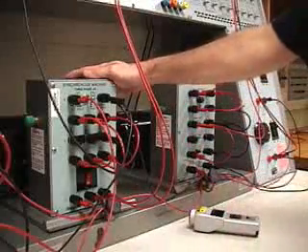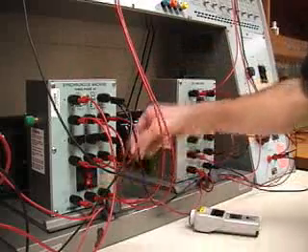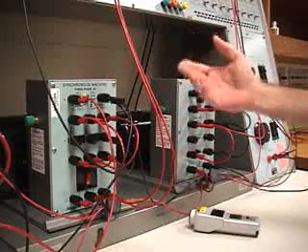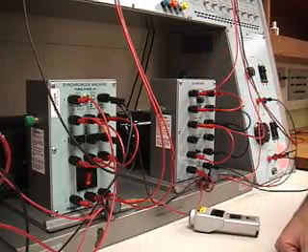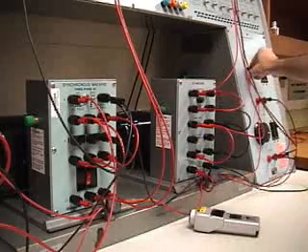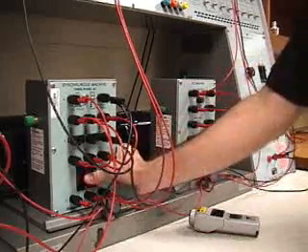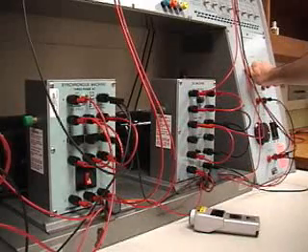In the startup of the three-phase synchronous generator, again the circuit breaker should be off initially and the load should be at zero value for when the circuit breaker is turned on. The synchronous generator before the load is connected, once you are driving it, you should adjust the excitation to get the voltage operating at a satisfactory level for the load before switching the load on.